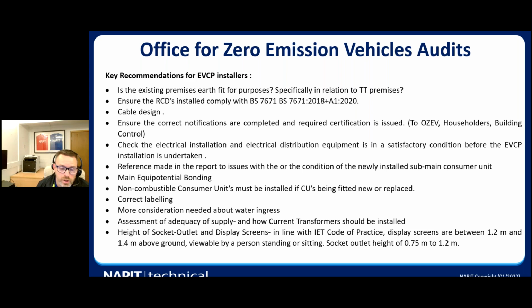And the height of the socket outlet and display screens in line with the IET code of practice. And the measurements are between 1.2 and 1.4 meters above the ground. And for the display system and for the socket outlets, between 0.75 and 1.2 meters.